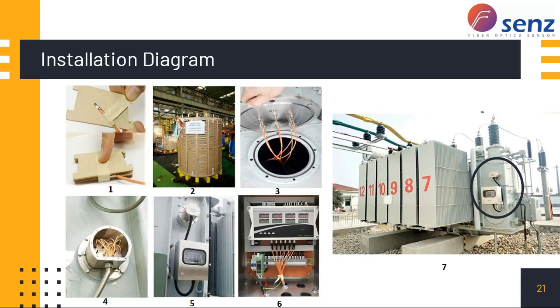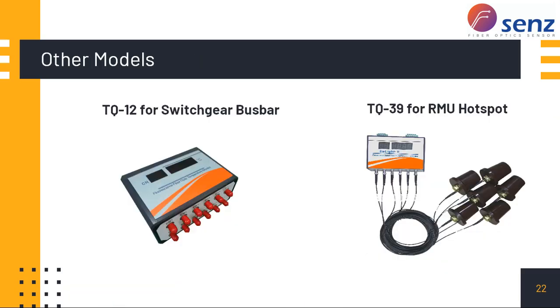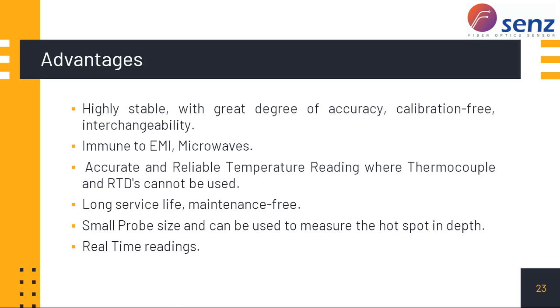These are real application examples of how and where to put the sensors in transformers. I have a plan for smaller ones, like this one for 12 channels, and it is also possible to provide a lower number of channels. It has high accuracy and is calibration free. The main thing is that it is immune to electromagnetic interference and gives a long-term reliable temperature reading. It is important for the long service life of the transformer. That was about the fluorescence based temperature sensors from Tempson.